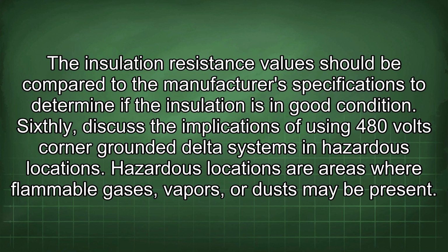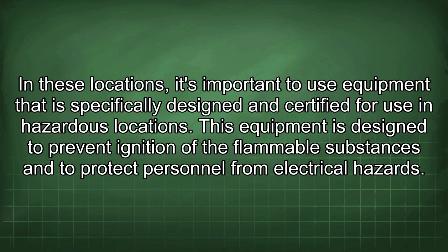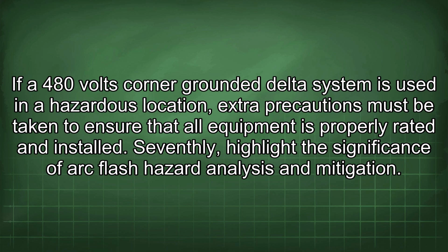Sixthly, discuss the implications of using 480 volts corner-grounded delta systems in hazardous locations. Hazardous locations are areas where flammable gases, vapors, or dust may be present. In these locations, it's important to use equipment that is specifically designed and certified for use in hazardous locations. This equipment is designed to prevent ignition of the flammable substances and to protect personnel from electrical hazards. If a 480 volts corner-grounded delta system is used in a hazardous location, extra precautions must be taken to ensure that all equipment is properly rated and installed.